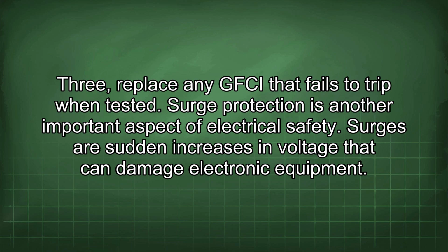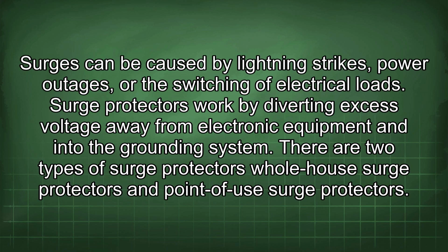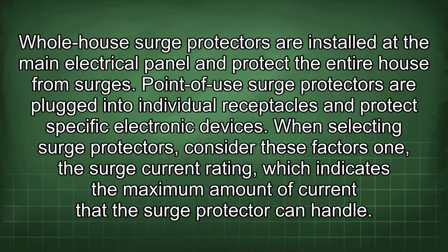Surge protection is another important aspect of electrical safety. Surges are sudden increases in voltage that can damage electronic equipment. Surges can be caused by lightning strikes, power outages, or the switching of electrical loads. Surge protectors work by diverting excess voltage away from electronic equipment and into the grounding system. There are two types of surge protectors: whole house surge protectors and point-of-use surge protectors. Whole house surge protectors are installed at the main electrical panel and protect the entire house from surges. Point-of-view surge protectors are plugged into individual receptacles and protect specific electronic devices.